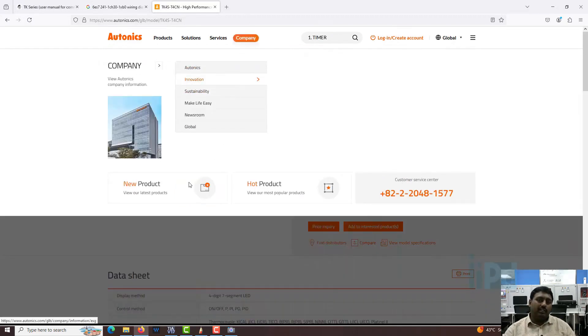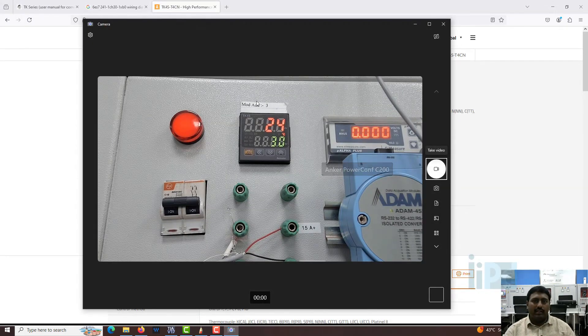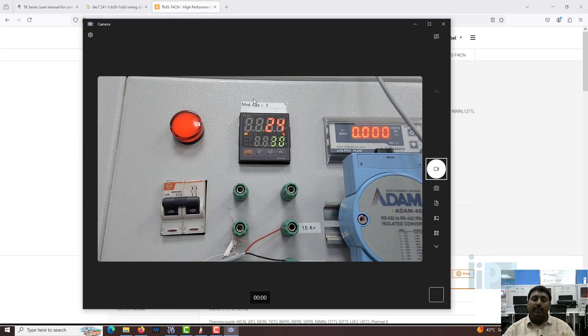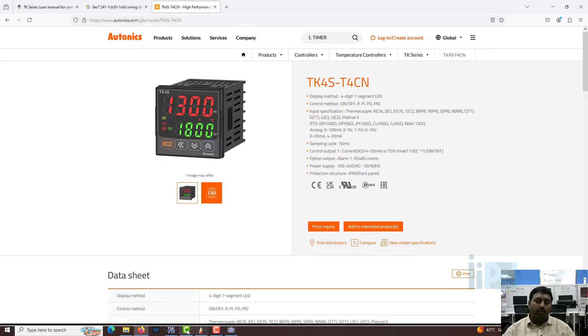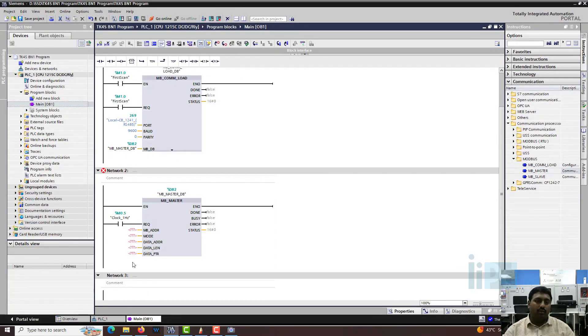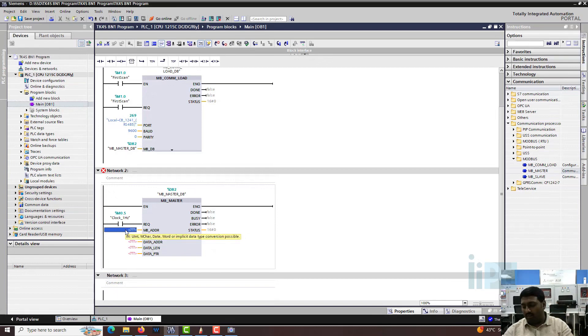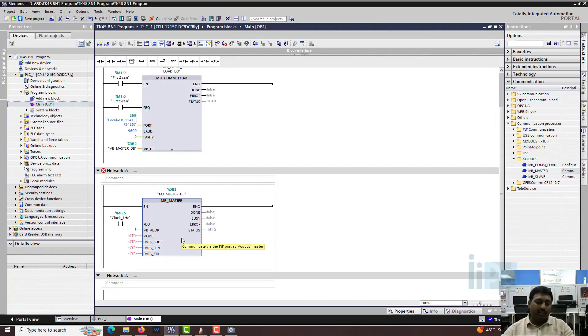As per the device image, the Modbus address is 3, the communication protocol is 9600 bits per second, eight data bits, one stop bit, and no parity - that is what we call 8N1. The MB_ADDRESS is the slave ID, so slave ID will be 3. The MB_MODE is very important.